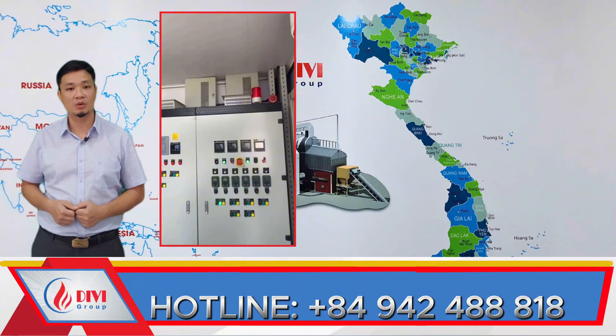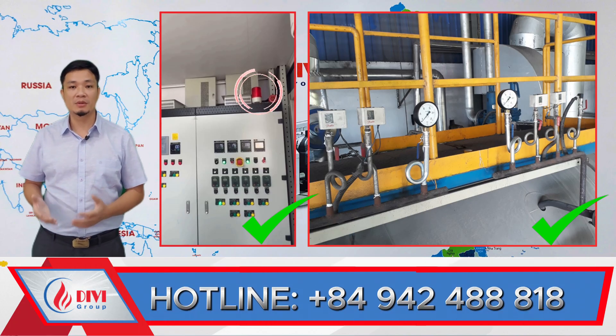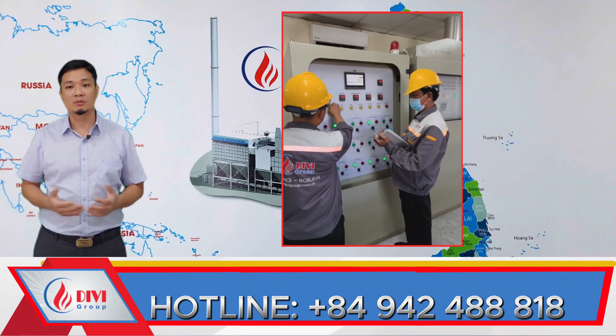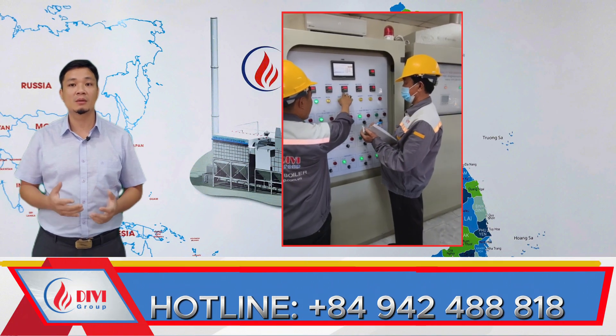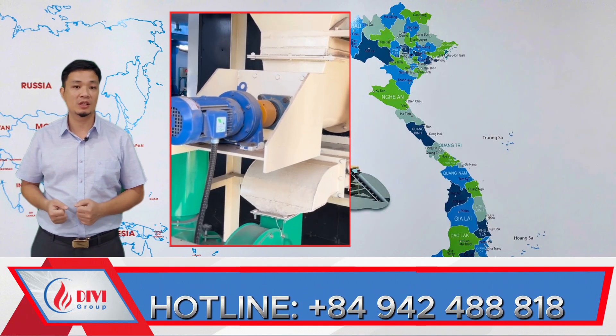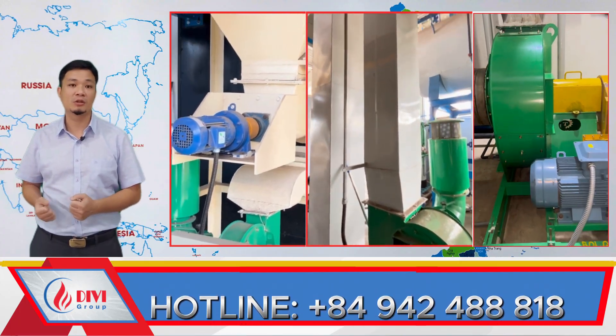Third, install proper alarm systems — you need clear low-pressure alarms, well-marked pressure gauges showing safe limits, and good lighting to make them easy to read. Fourth, never let new operators work alone; always have experienced staff supervise them until they fully understand how to adjust fuel, air, and pressure settings safely. Fifth, perform regular maintenance on key components like the screw feeder, conveyors, air fans, and exhaust fans.